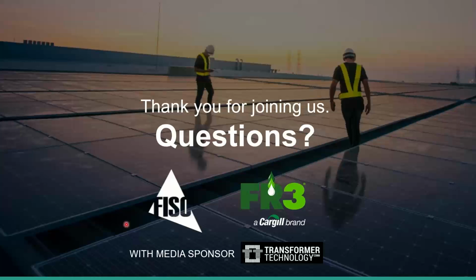Yeah, if you allow me, this is Alan, just to offer some help here on this one. So the permittivity, the dielectric constant of FR3 is around 3 at 90 degrees, and mineral oil is 2.2. So there is a different distribution of electrical field and stresses inside the transformer due to that. In general, reducing the stress in the fluid and increasing the stress in the solid insulation.